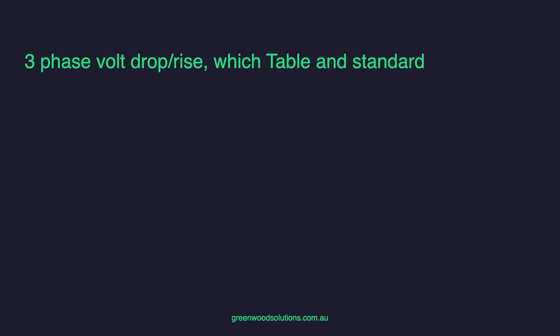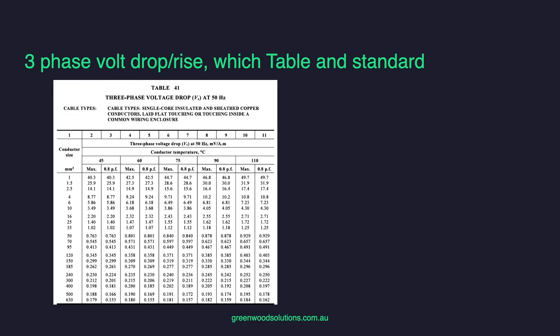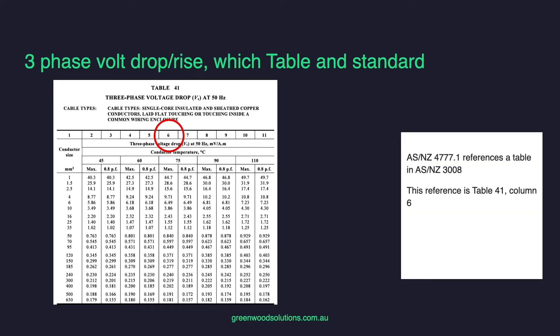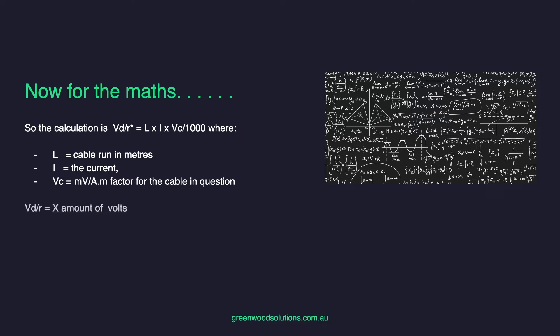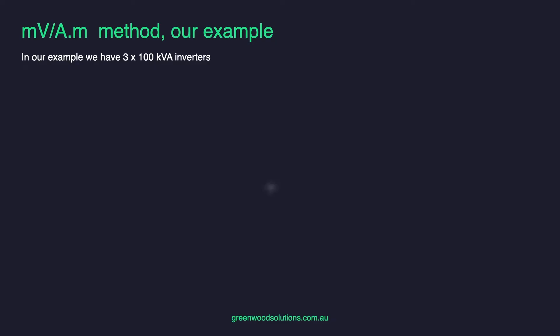AS4777.1 references a table in AS3008 — you've got to know AS3008. This reference is Table 41, column 6, as you can see in the table below. The calculation is: V rise equals L times I times VC, divided by 1000. Where L is the cable run in metres, I is the current, and VC is the millivolt per amp metre factor for the cable in question. The volt rise result is in volts, and volt rise and volt drop are mathematically the same calculation.